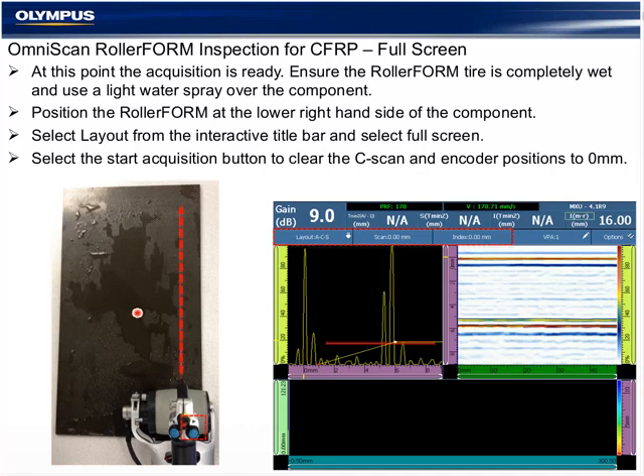So we will select the Start Acquisition button here, and that will clear the C-scan here. It will reset the scan and index encoders at 0, 0, preparing us to take the acquisition. We would normally be in full screen mode from the layout on the interactive menu. In full screen mode, I don't see the menu options here or here, and we see a much larger area of real estate on the display for our actual data.